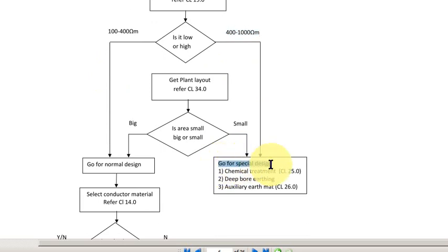Then you have to go for special design. When I say special design, you have to go for chemical treatment, or you have to go for deep bore earthing, or you have to go for auxiliary earth mat. Now, these extra things are required to achieve a low resistance in spite of high resistivity.